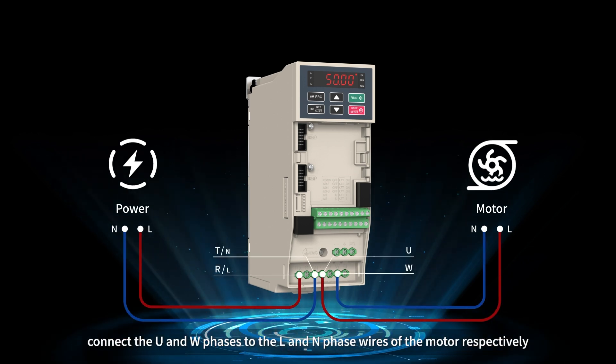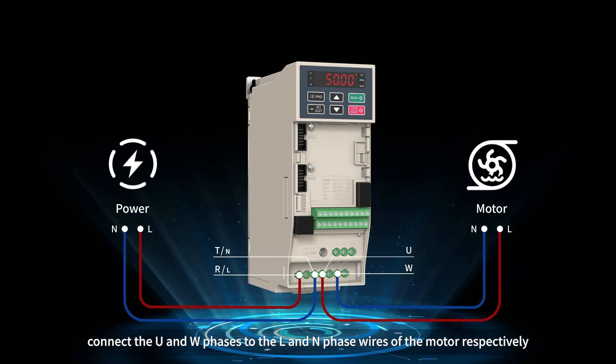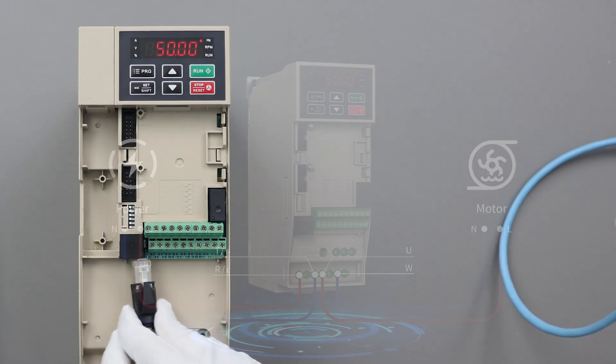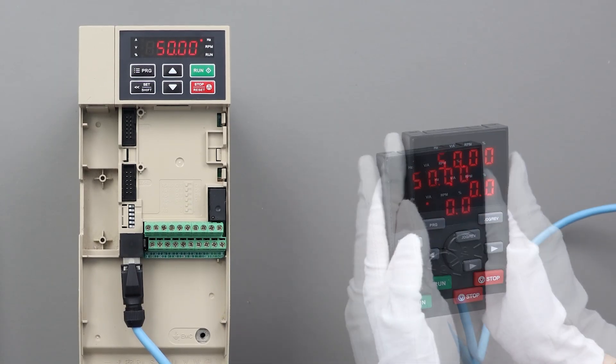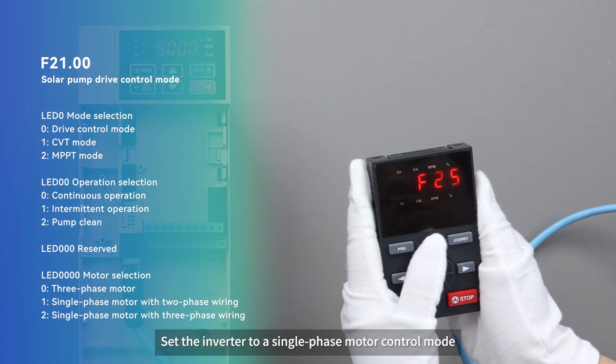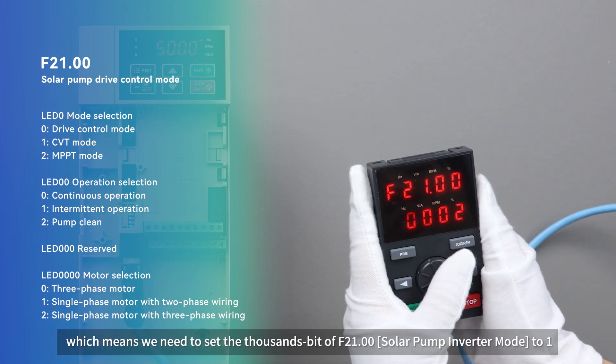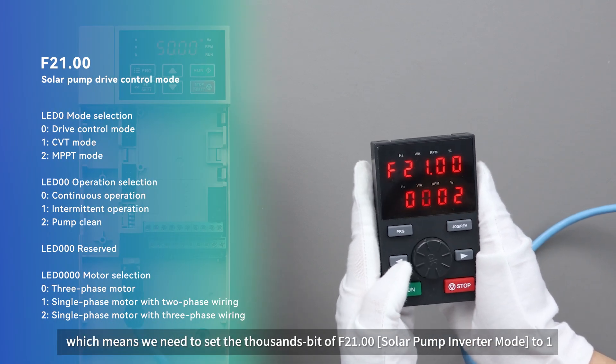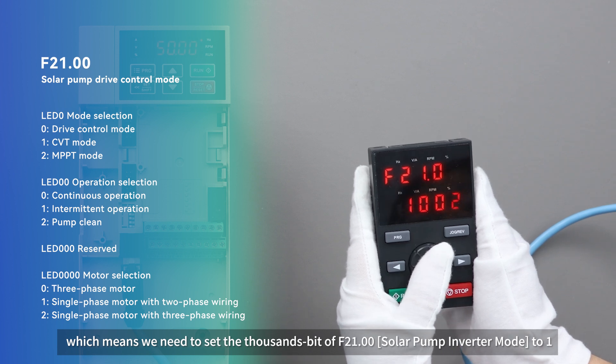Connect the U and W phases to the L and N phase wires of the motor, respectively. Set the inverter to a single phase motor control mode, which means we need to set the thousands bit of F21.00 to 1.